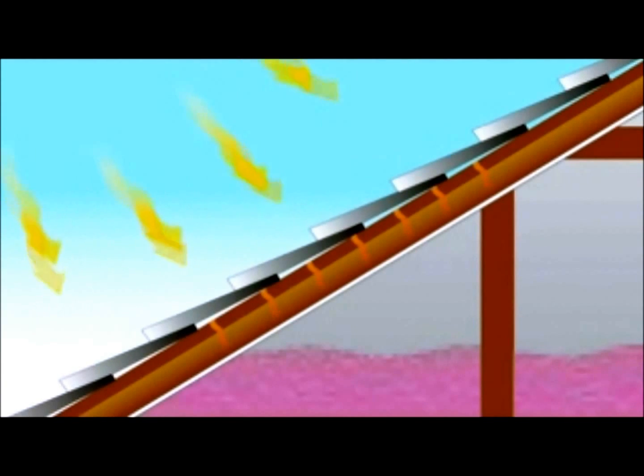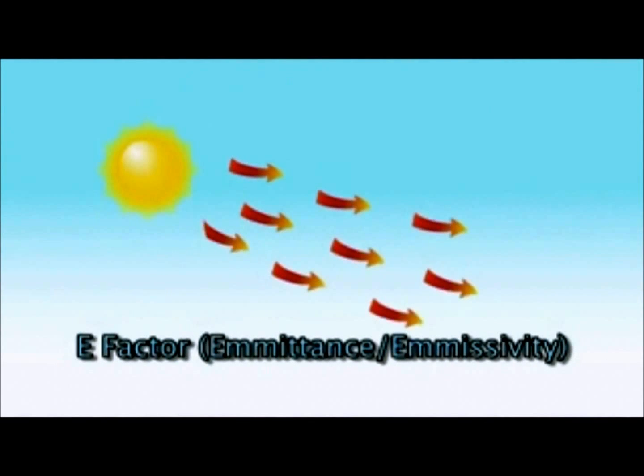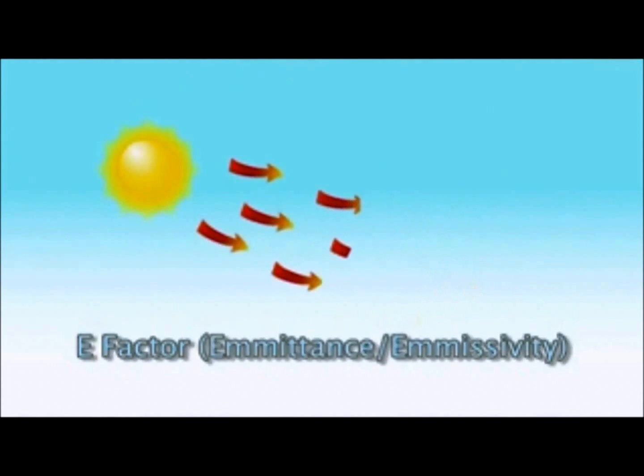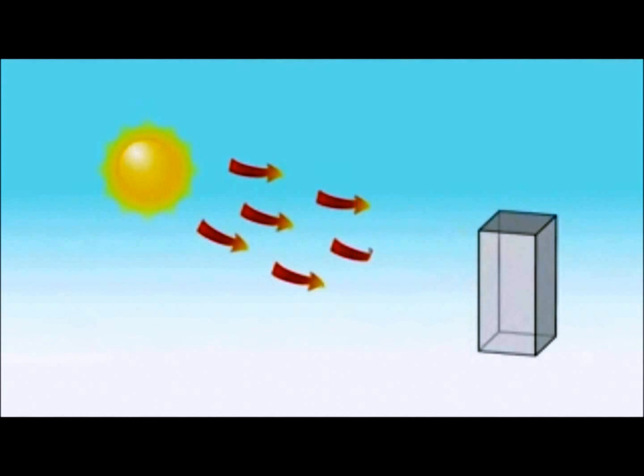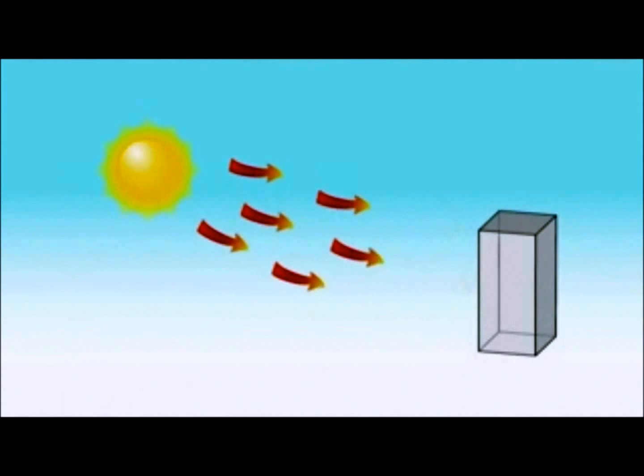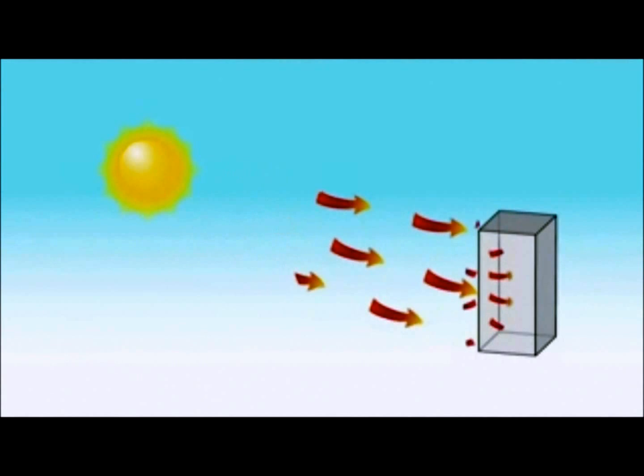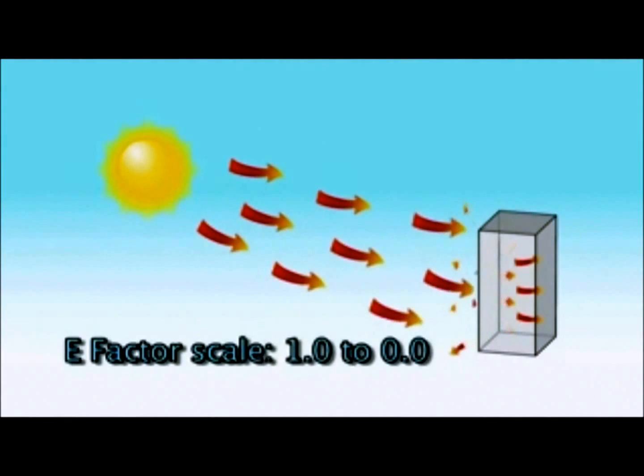and the ductwork sending the cold air through the attic area. To understand radiant heat transfer, we need to discuss several topics. Radiant heat is measured using e-factor, which stands for emittance or emissivity. Radiant heat always moves from hotter to colder, and radiant heat doesn't do anything until it strikes an object. When it strikes something, the energy does only a combination of two things, and that is how we come up with its e-factor.